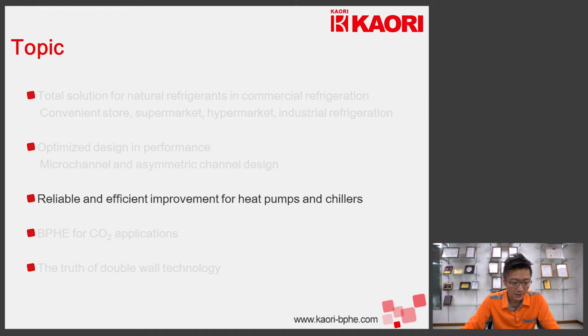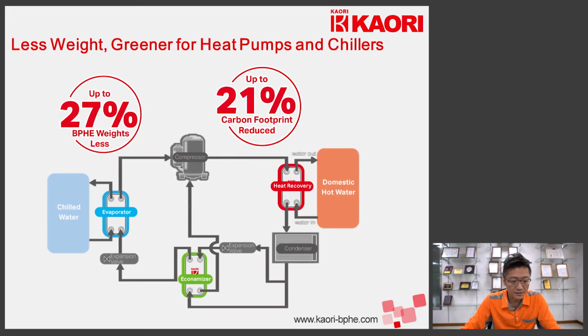In this topic, let's look at an example of the reliability and efficiency improvements for heat pump and chillers. This is an example of an air chiller or heat pump. The evaporator, economizer, and heat recovery unit require brazed plate heat exchangers. If we replace these 3 brazed plate heat exchangers with microchannels, they can be reduced in size and weight by 27% compared with standard conventional brazed plate heat exchangers, and also save 21% in carbon footprint during the manufacturing process.